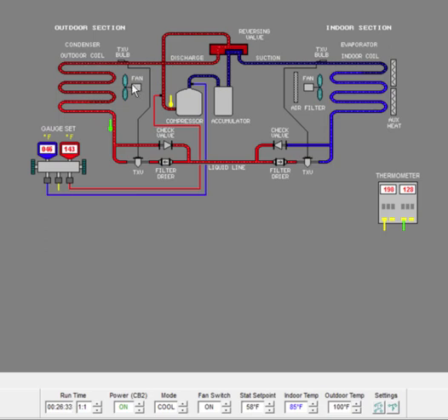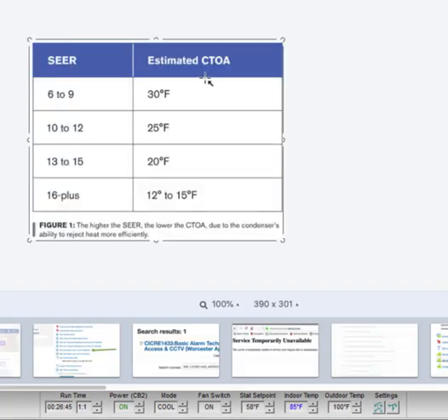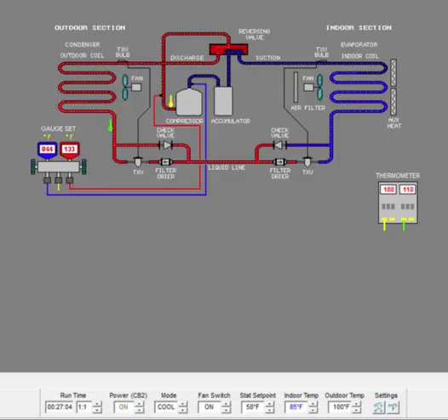Believe it or not, sometimes people replace the fans and the fan blade is not positioned exactly properly within the condenser itself. So all of this is affected by this condenser to outdoor air temperature, and this is a pretty important chart to have. So again, this was brought up recently in an article in Air Conditioning Refrigeration News. The tech tips in that newsletter are awesome. Get a copy if you can, but always check your outdoor air temperature to your condensing temperature.